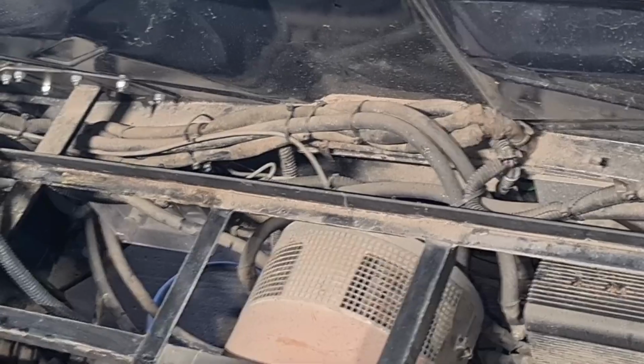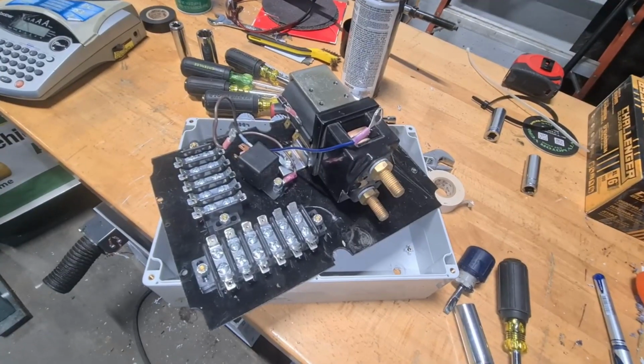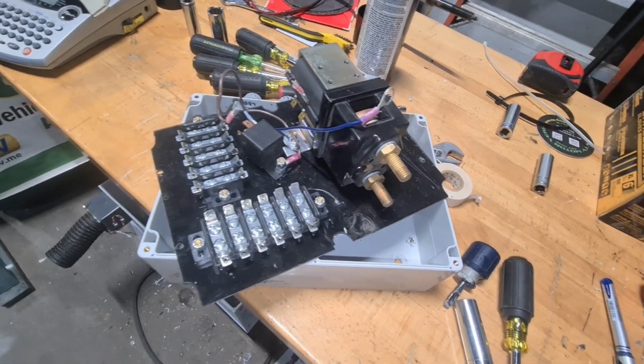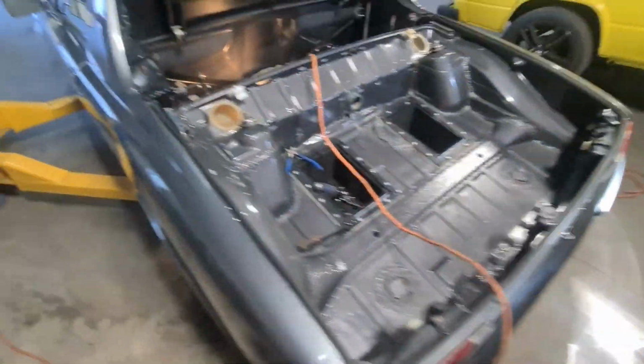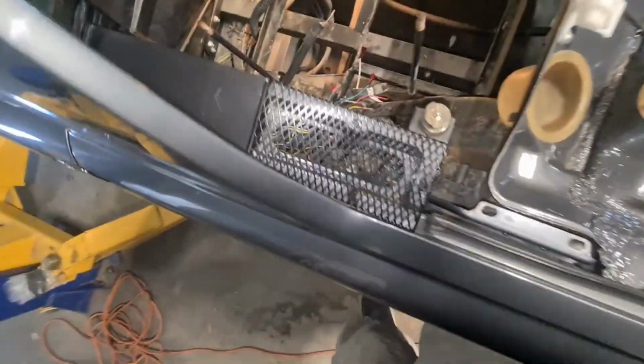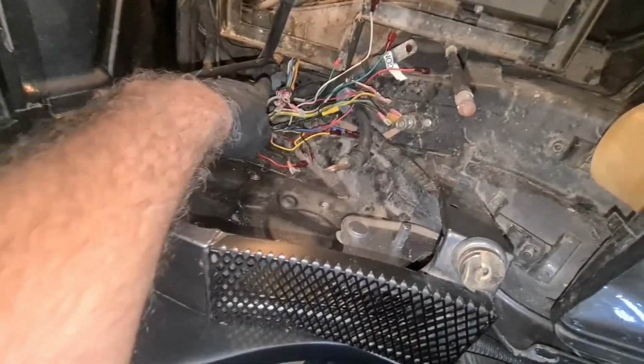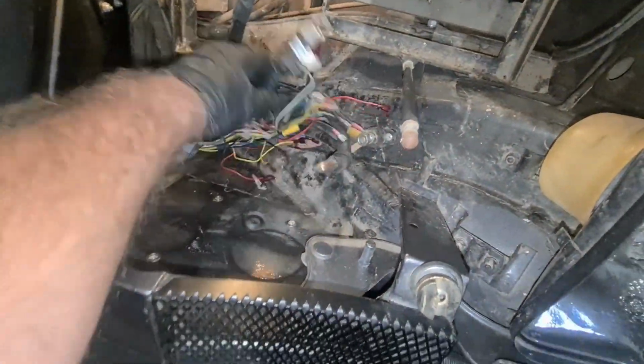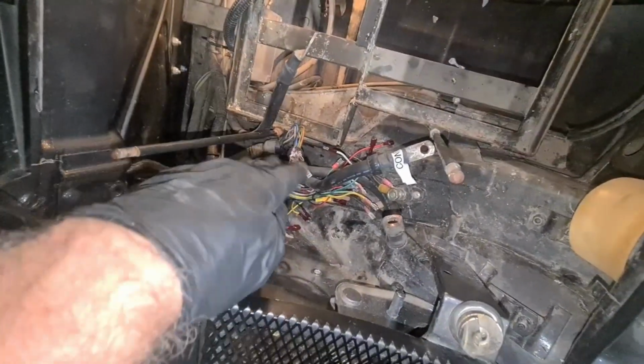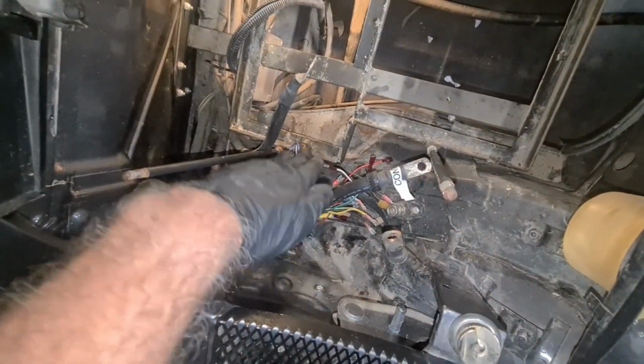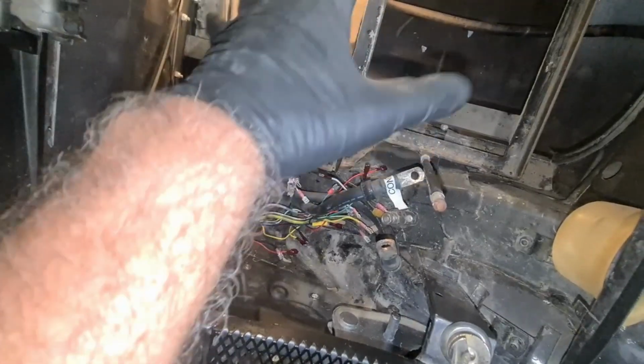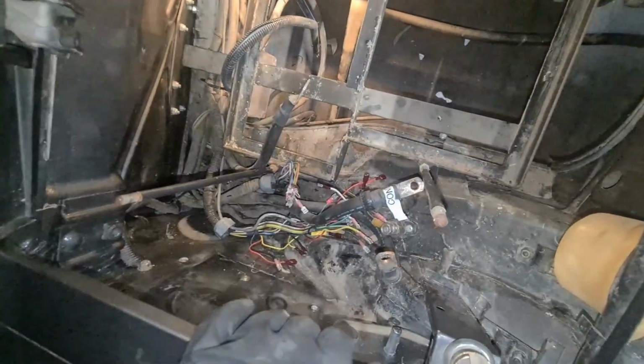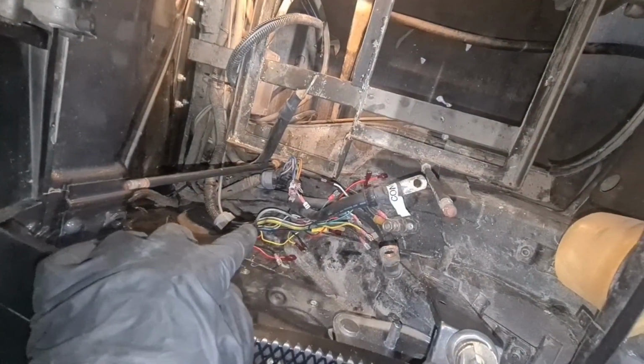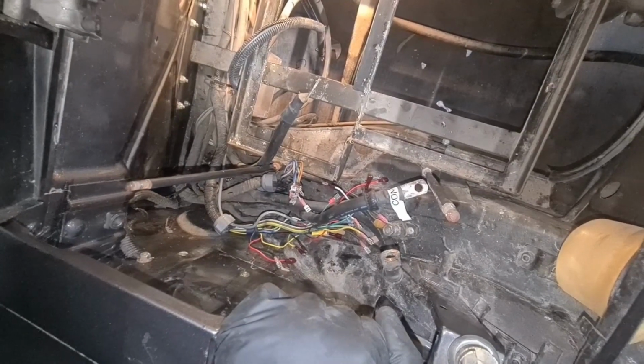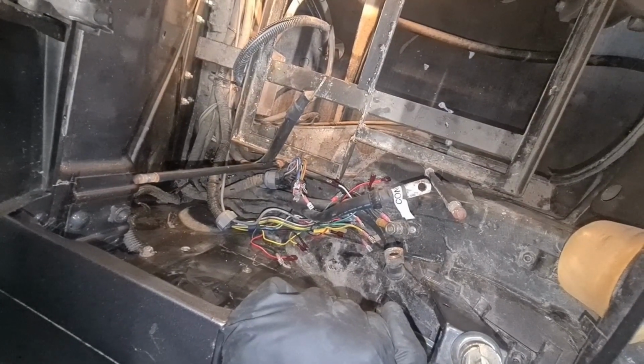Must resist the urge to clean. Now the contactor box is out, and I remember why I hated it so much. These are all the remnants here, all the low voltage stuff and the DC, which I can now pull through. If anything went wrong in that box, it was basically trapped here, and I would have had to do the entire disassembly of everything you've seen here just to fix maybe one wire. I won't make that mistake again.